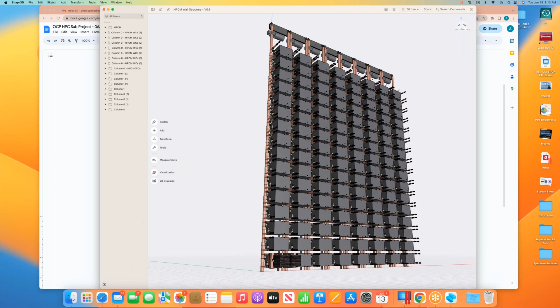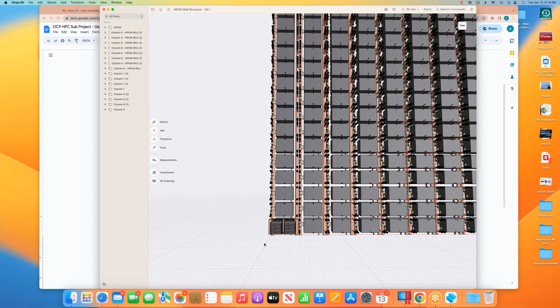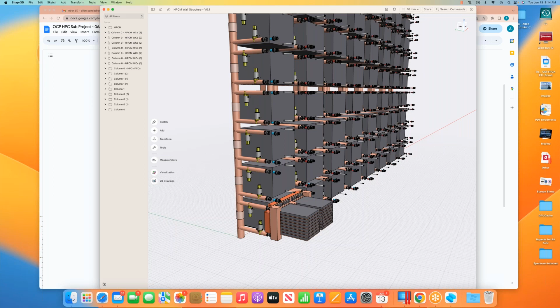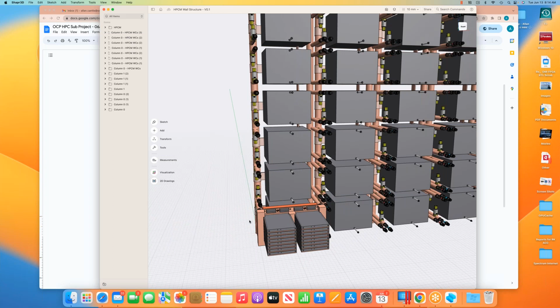The key thing, when I was explaining it, is we want the return hot water to be 65 degrees C for energy recovery. So we were talking about having a couple of variable valves on the inlets, and measuring the temperature on the outlets, so that depending on the power of each module, you'd be able to cool it appropriately to get 65 degree C water out of it.